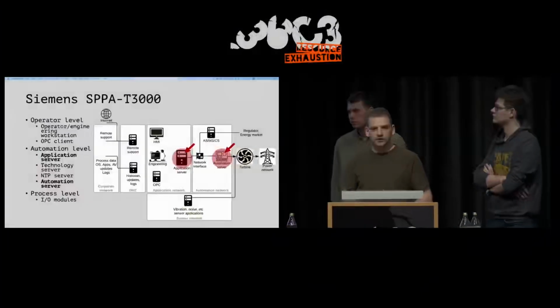Despite the fact that if you read the manuals for the Siemens systems, there would be a lot of different networks, highways, and claims that there is no connection between the application network and external networks, in practice and in reality you will find things like a specific sensor network, for example monitoring vibration, foreign objects, and some noises inside the turbine.